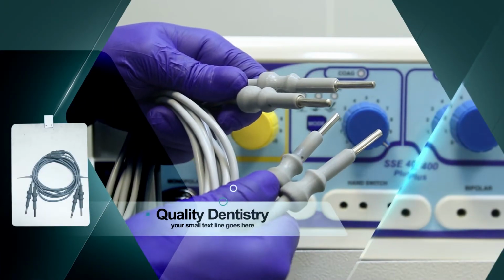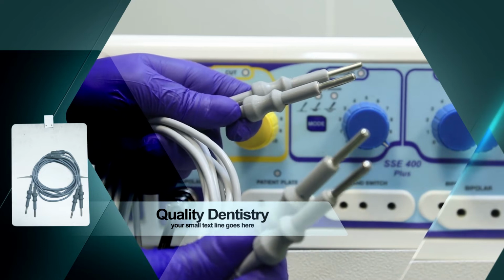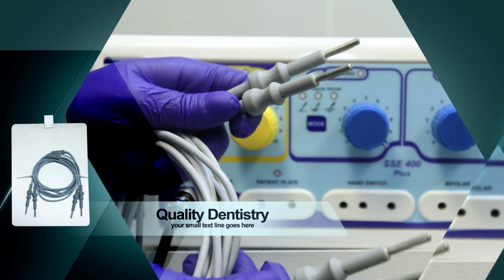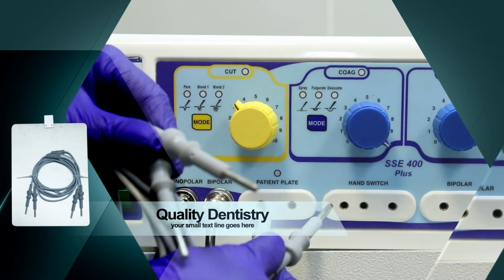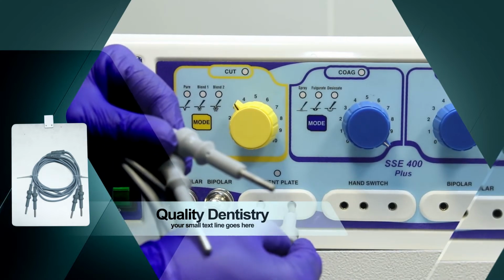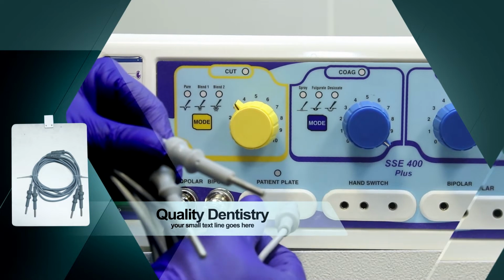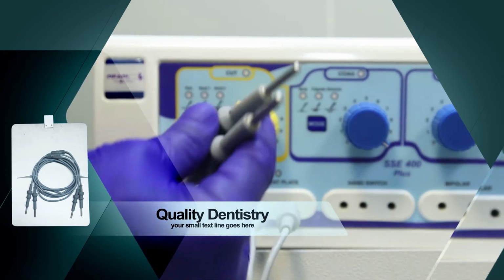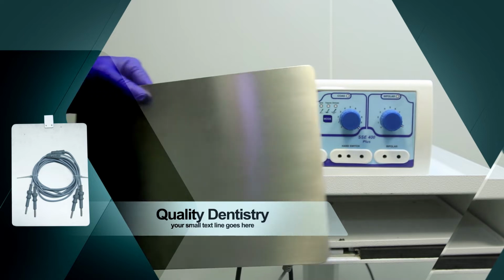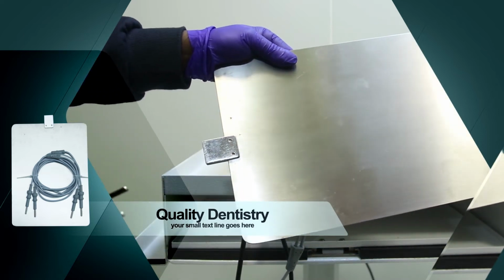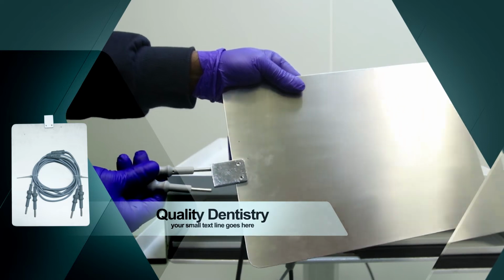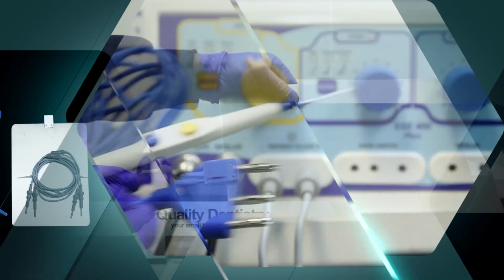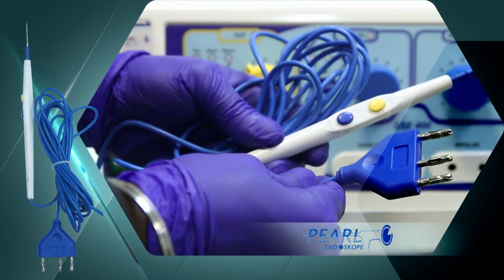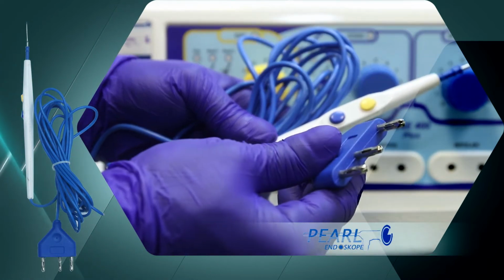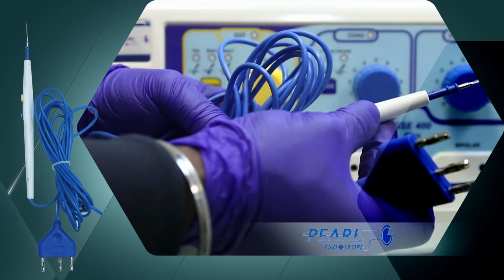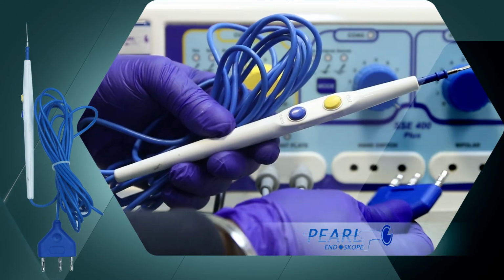This is the patient plate, and the cables are connected as shown. These ends are connected to the patient plate port. This is the patient plate, and the cables from the machine are connected here. This is the monopolar hand switch, which is disposable. This point is connected to the machine, while this point is for the patient's body.